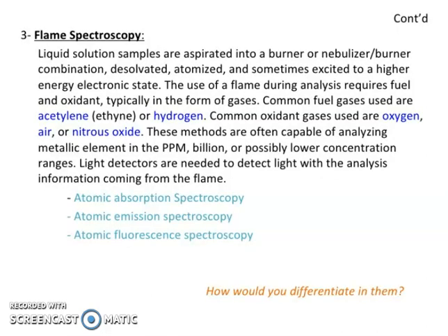Now, friend, flame spectroscopy. Liquid solution samples are aspirated into a burner or nebulizer. In the burner, the combination is desolvated, atomized, and sometimes excited to a high-energy electronic state. The use of flame during analysis requires fuel and oxidants, typically in the form of gases. Common fuel gases used are acetylene or hydrogen. Common oxidant gases used are oxygen, air, or nitrous oxide.